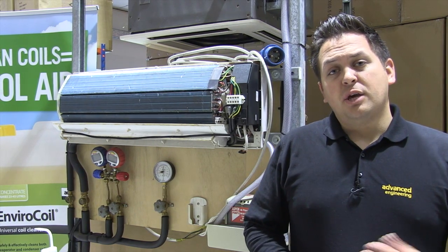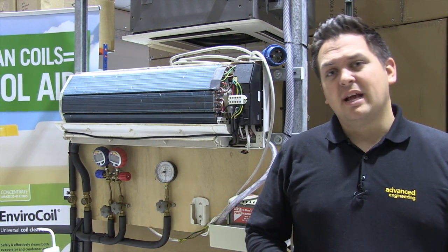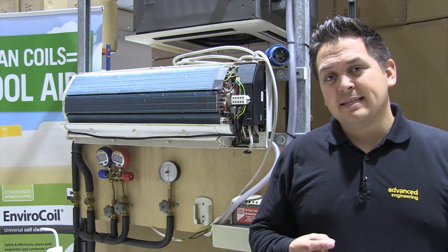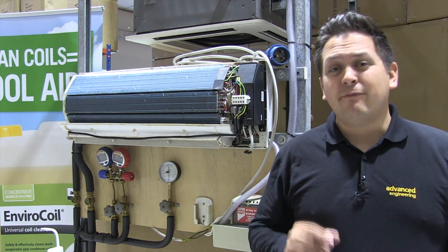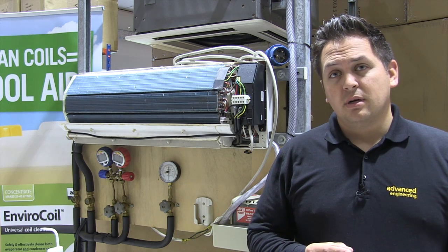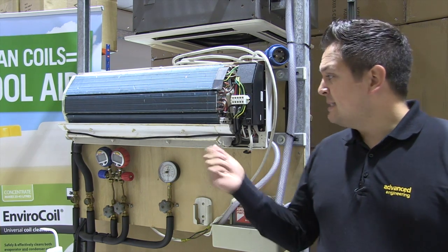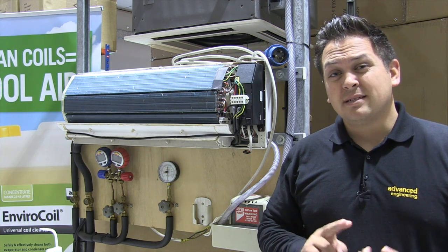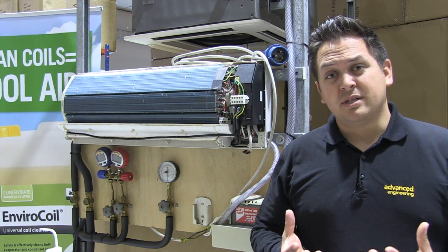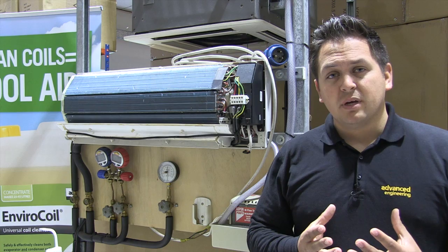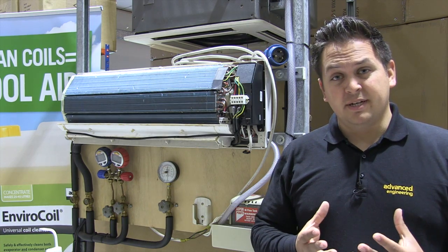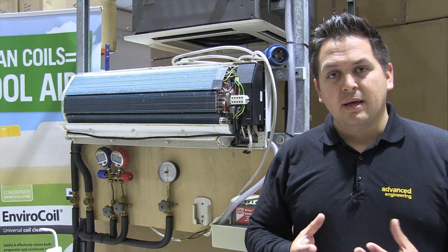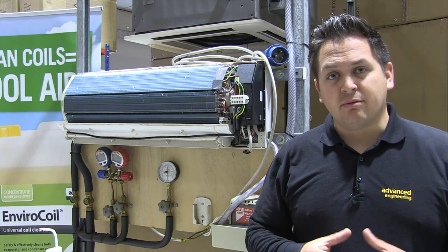Interestingly, the human body sheds between 3,000 and 2 million skin cells per minute, and attached to those skin cells is between 2 and 4 microorganisms. Now they can be transported into the air conditioning system where it's dark, damp, moist, and these conditions are typical conditions for bacteria to grow. Now bacteria, whilst in those conditions, will secrete a jelly called exopolysaccharide that will protect them from environmental threats.